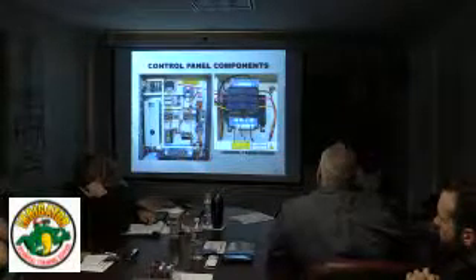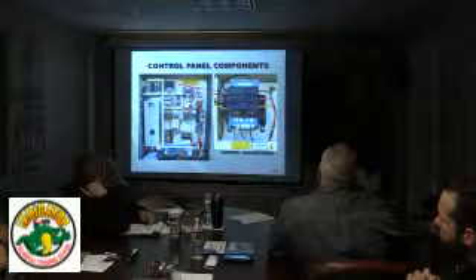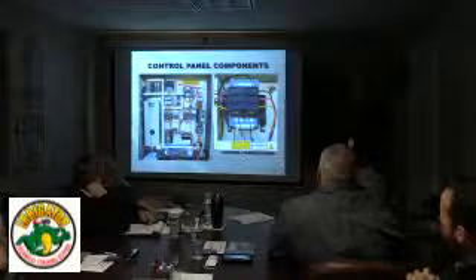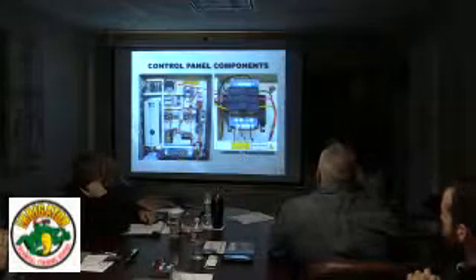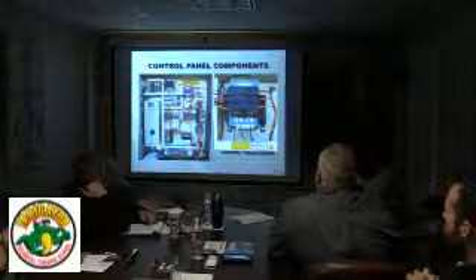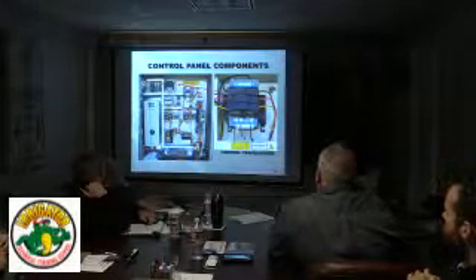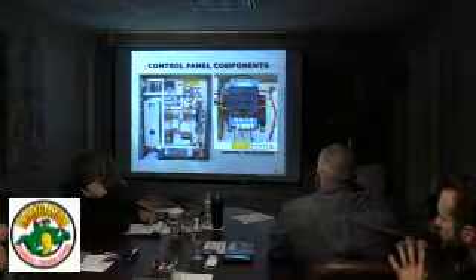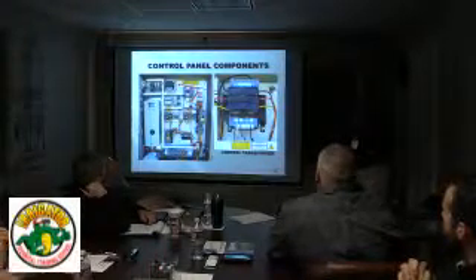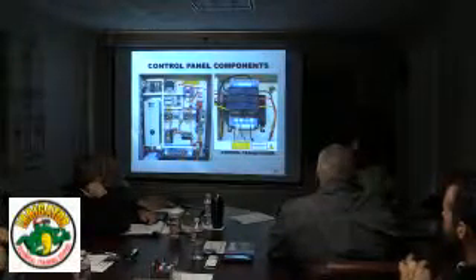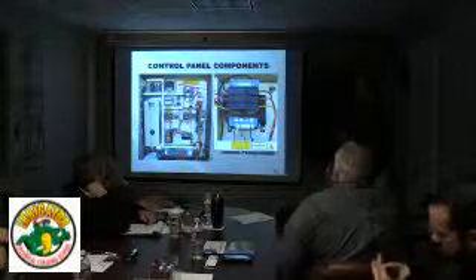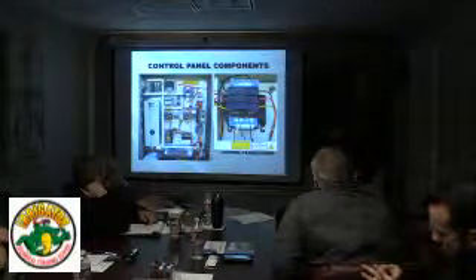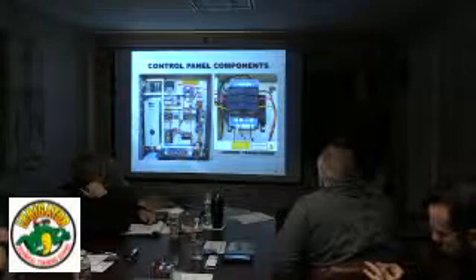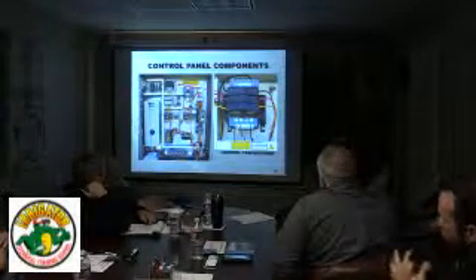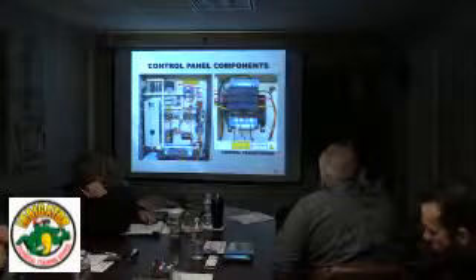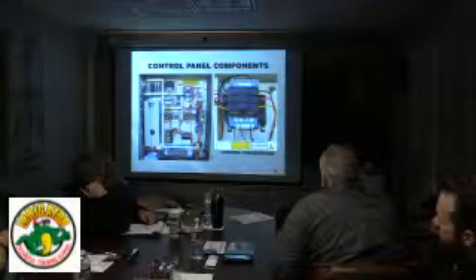So if everything in the panels is gone, you don't have any power, this will be the first thing that you would look at, these fuses on here. Make sure you got 480 coming into it. Check these fuses. They do have finger tabs on them where you can just pull them out. I'd still turn the power off and just pull them out, check them with the meter one at a time. Check those fuses, see. You should get 480 across the top here, and then that would give you 120 across the bottom here. So you can measure that too.